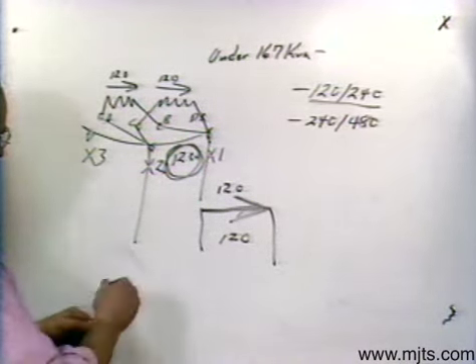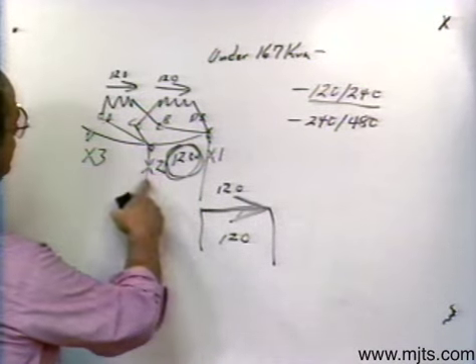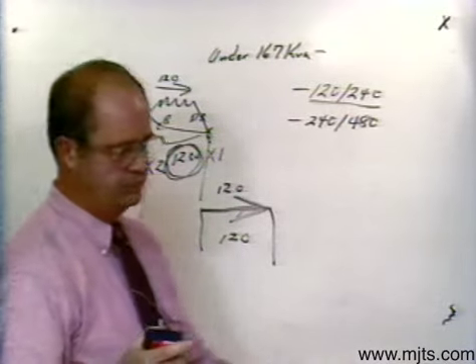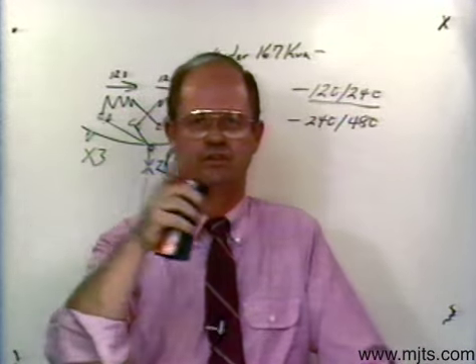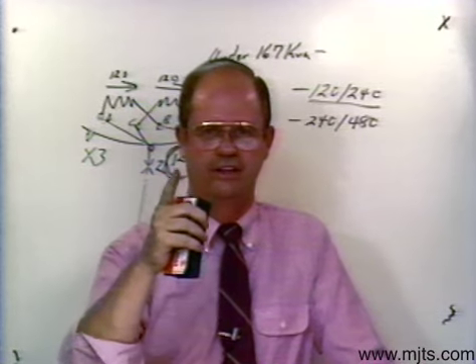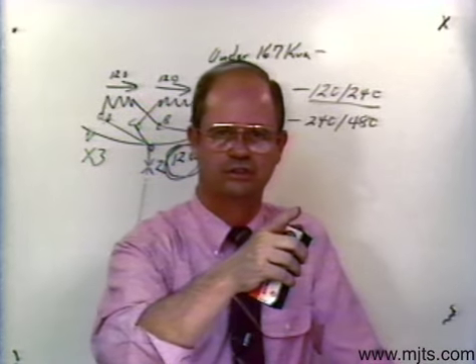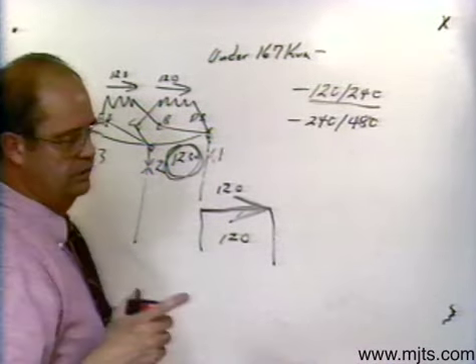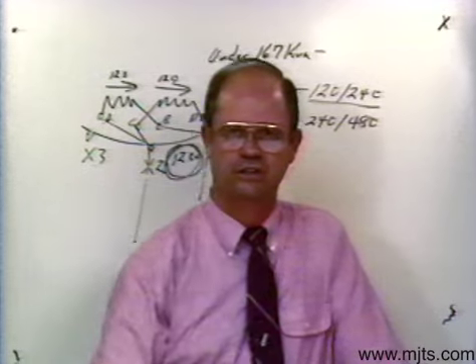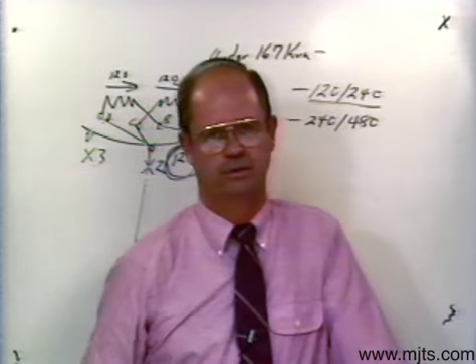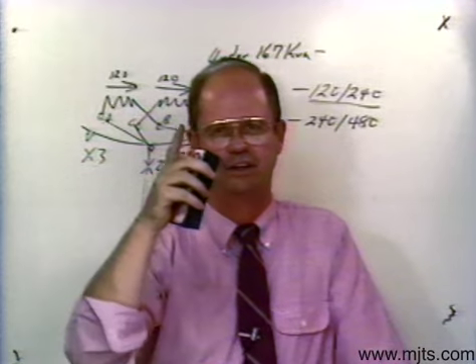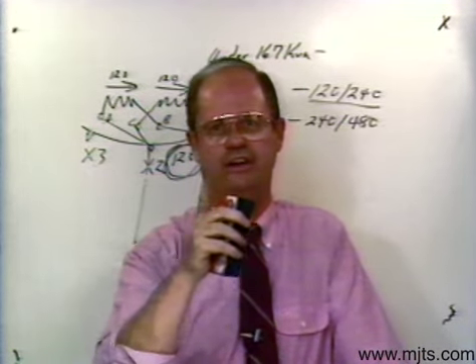There is a reason why we want to parallel it in that fashion. If a transformer is paralleled and you use anything other than X1 and X2 — let's say you use X1 and X3 — and you take that transformer out of service and don't restore it back to normal series connection, then if somebody puts that in a residential service, you would supply low voltage across loads that normally want 240 volts and potentially burn up appliances.